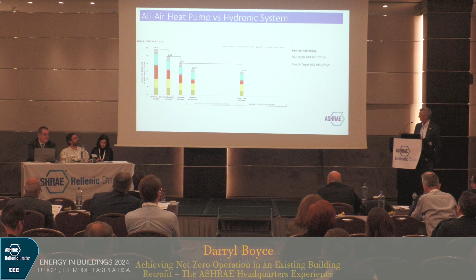And so we ended up with the hydronic system, as I said, smaller modular control, simultaneous heating and cooling, heat pump and/or heat recovery machine. So a heat recovery chiller was utilized, to decouple the temperature from humidity. So we had a DOAS unit that would reduce the humidity in the building and provide 1.3 times the minimum ventilation air, per ASHRAE 62, and also had a heat recovery wheel within the unit. We have staged pumping, water source heat pumps for transient or potentially humid spaces, so there were some water source heat pumps throughout the building, and overhead radiant panels for heating and cooling.